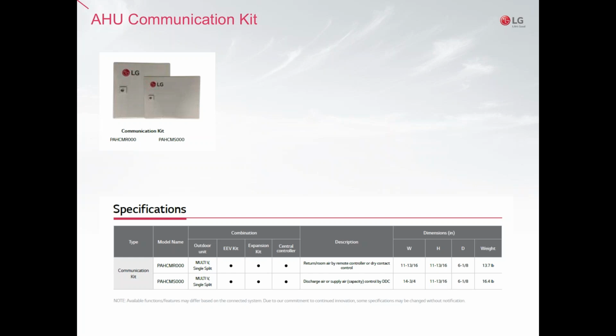But if the unit is needed to supply outside air and the temperature to control would be the leaving or discharge air temperature after the DX coil, then you will need the supply air temperature controller, or PAHCMS000. These are typically controlled by a sensor downstream of the DX coil in the ductwork. There could be a couple of very specific exceptions to this rule, but these are not typical applications.